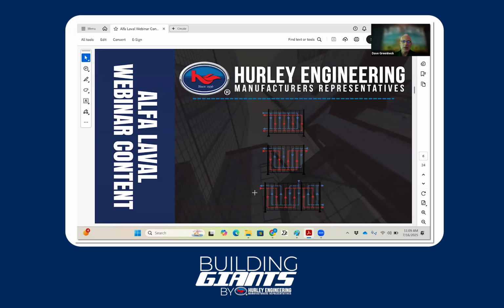This third example illustrates multi-pass but with multiple sections. This thicker vertical line represents basically a second heat exchanger, married up in the same package for convenience, but it's a separate exchanger. The hot fluid does two series passes, collects, and continues to a third series pass. The cooler fluid, maybe glycol at 20 degrees or colder, is in its own section making its own pass. So: single pass, multi-pass, and multi-pass with multiple sections.